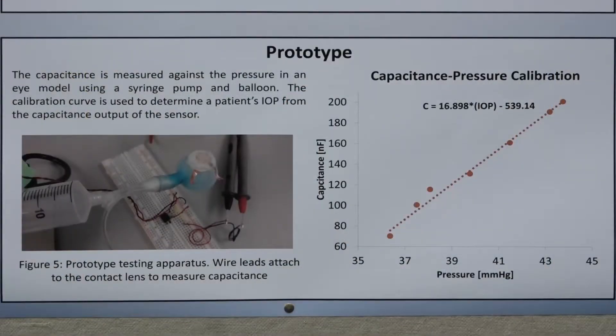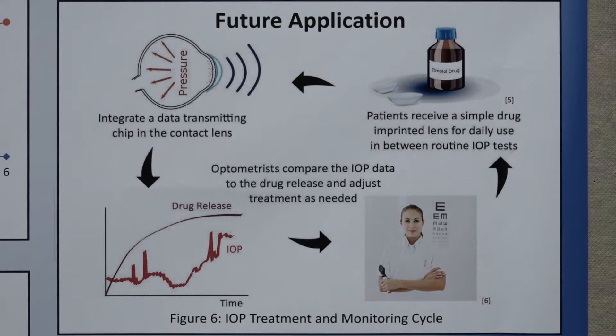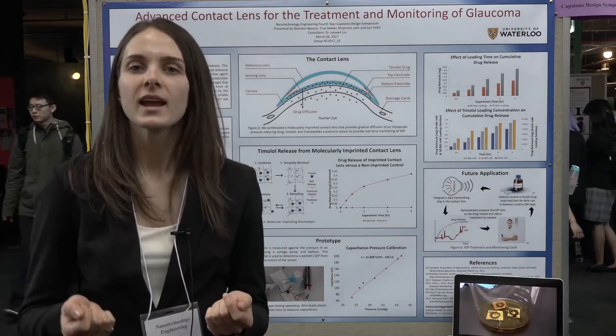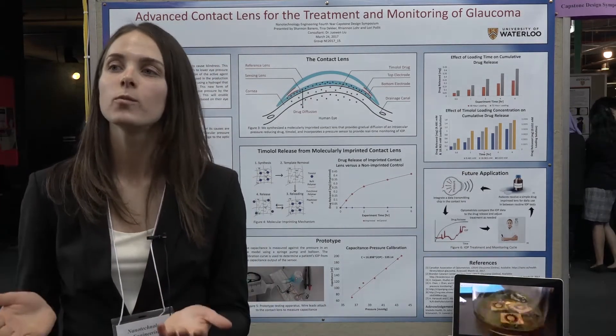The big picture is to create a glaucoma treatment and monitoring cycle, where a patient will go to an optometrist's office and wear the contact lens with the pressure sensor and drug release for a 24-hour period. Using wireless technology, like an RF chip integrated into the sensor, this data will be transmitted to a device available to the optometrist. The optometrist can then look at the IOP trends, compare them to the drug release, and adjust the prescription as needed. On a daily basis, the patient will receive contact lenses that are a single layer containing the drug-releasing lens.